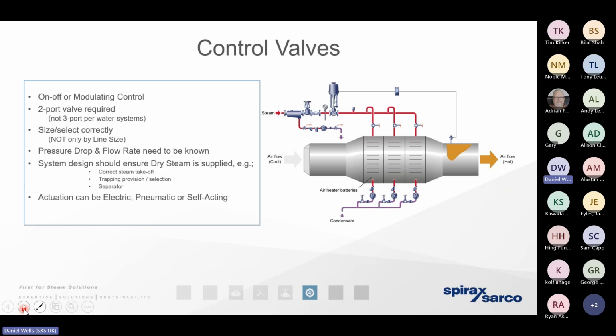So, things to bear in mind when we're looking at how we use steam at the point of use, areas for optimization. Some of those critical, temperature sensitive applications will be controlled with an actuated control valve. It could be pneumatically or electrically actuated. Very, very sensitive, very, very smooth, sensitive surface areas. Typically, they're going to be metal to metal seated valves. And quite often we come across problems with control valves whereby they're oversized.